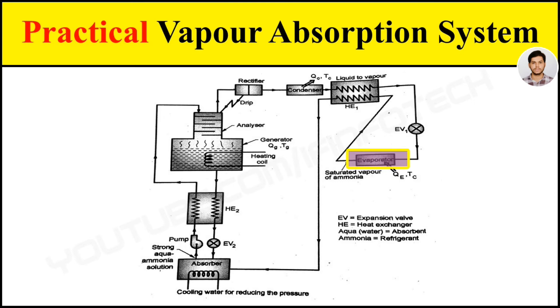The refrigerant absorbs heat in the evaporator and passes to the absorber through the heat exchanger. In the absorber, cooling of the refrigerant takes place by the weak solution from the generator, which absorbs more ammonia. The mixture from the generator and the strong ammonia are mixed in the absorber to form a strong aqua ammonia solution.